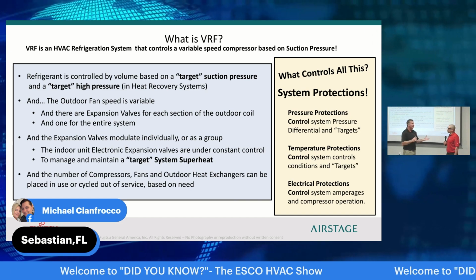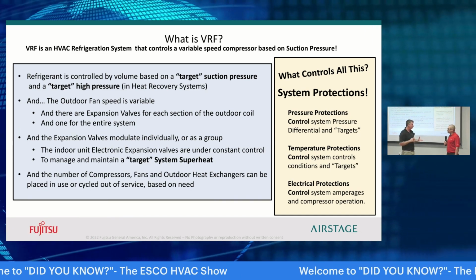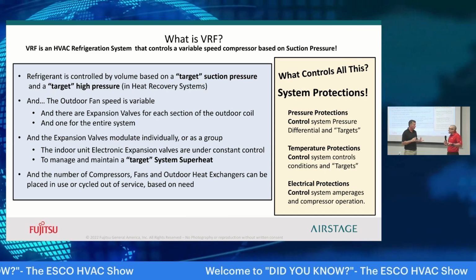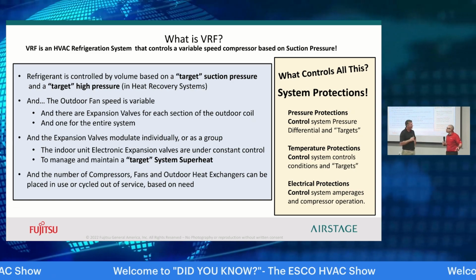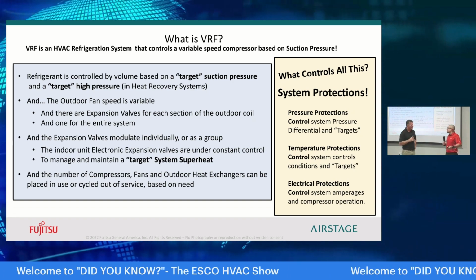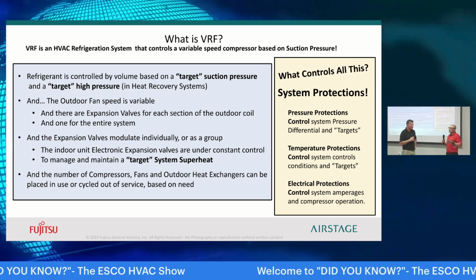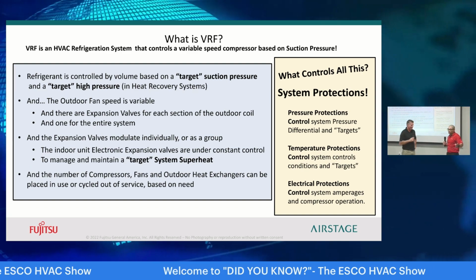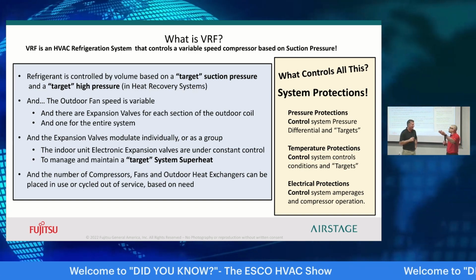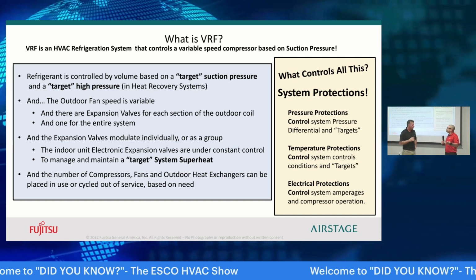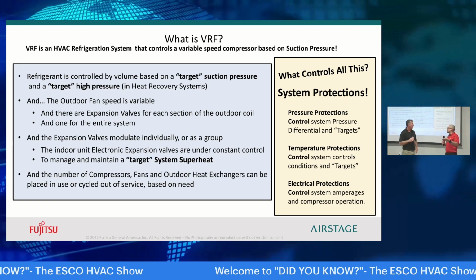And then we come to class and learn what's different about it, right? But it's actually exactly what we know already. It's the same refrigeration system. You still have subcool, you still have superheat, still got a compressor, a condenser, still have a metering device. You still have indoor units, but you have multiple indoor units, and the refrigerant is controlled depending on the need.